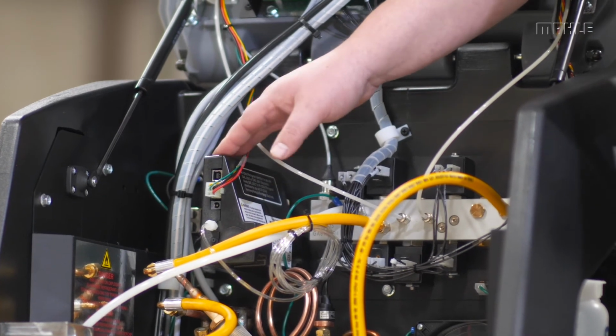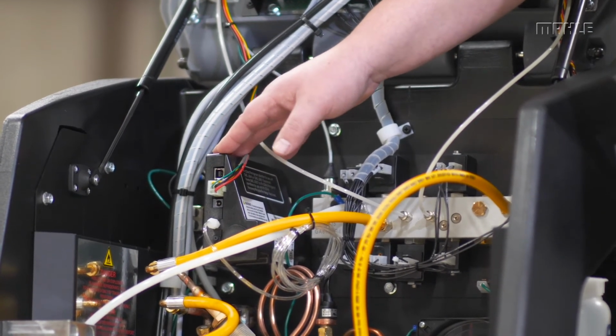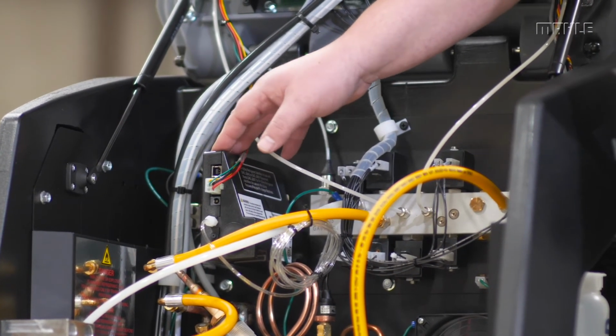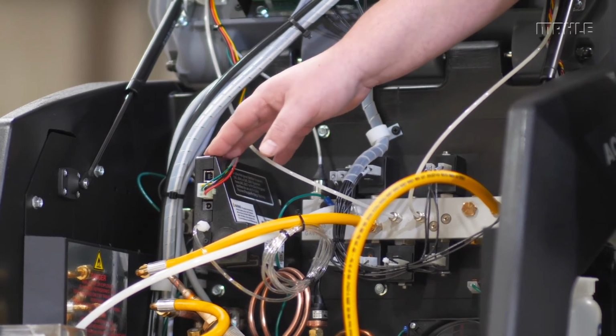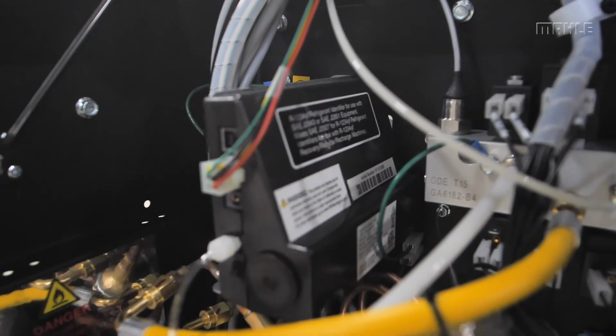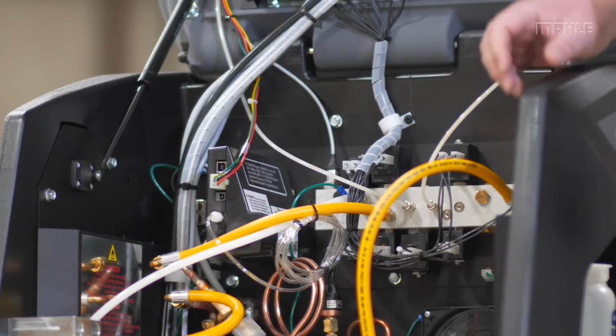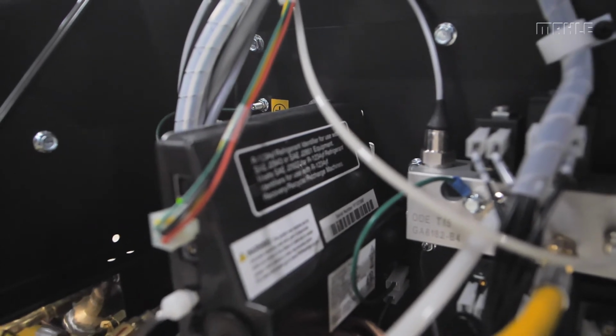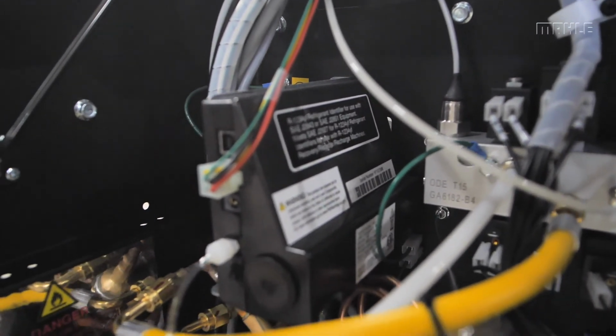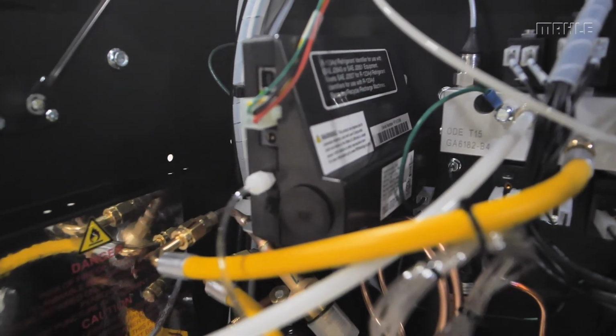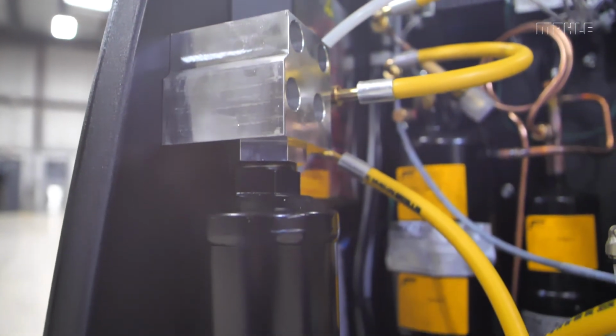They pull in stronger, and they're less prone to dirt and contamination inside the solenoid plunger. To the left, on this particular unit, we have an external refrigerant identifier that's internally mounted, and this prevents contaminations from entering the unit that would require a decontamination process. This is a great feature for preventing contamination, and if the unit does get contaminated, you just have to replace the refrigerant identifier.